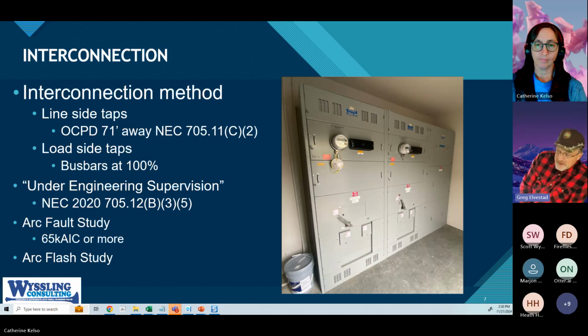You can. And that's still a real thing that is an option for you to do. But what if the switchgear is old enough that you can't find a breaker that you can derate down to? What do you do in that situation? Well, this is where under engineering supervision comes into play, and the code article is cited here. It's a little different for the 2023, it's B36, but the same thing is in play. You can interconnect a PV system under engineering supervision, provided that you evaluate the building load and perform an available fault current study on the service. And that's it. Very, very simple.